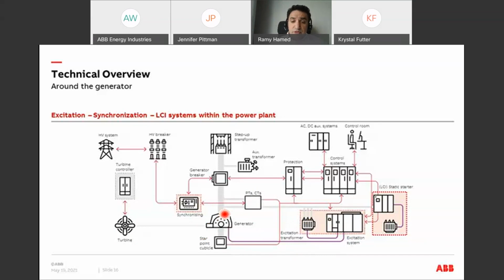The second main component that we wanted to talk about today is the synchronizing relay. Why do we need the synchronizing relay? Basically, after we generated the voltage here, the generator will need to be connected to the grid. And to connect to the grid, the generator breaker will need to be closed. However, these voltages are not exactly the same. And so before we can close the generator breaker, these two voltages need to be synchronized. So there are 4 synchronizing conditions that need to be fulfilled.